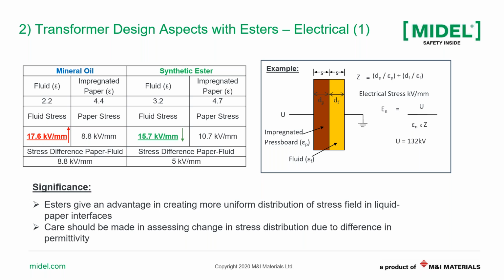The liquid is a dielectric fluid. Now, any dielectric material, dielectric fluid, has a permittivity parameter. And the permittivity parameter contributes to how the electric field, the electric stress, is distributed within the insulation system. So here we show an example of how a change in permittivity of the liquid can alter how the stress is distributed between the insulation materials of the transformer. We know that the insulation materials of the transformer are composed of paper and liquid, pressboards and liquid gaps.